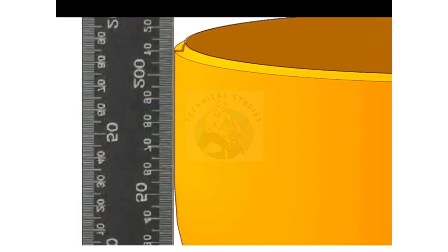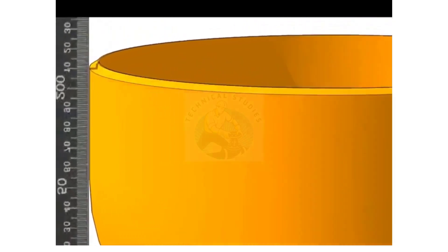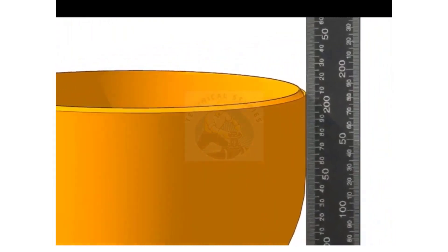Check the other sides also. If you find any gap on any side, equally divide it on both sides by giving shim plate at the bottom of the reducer.